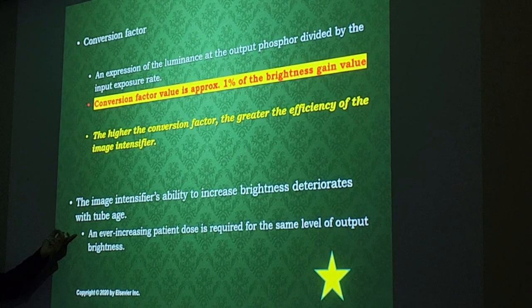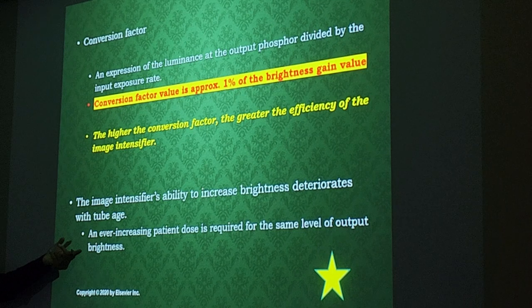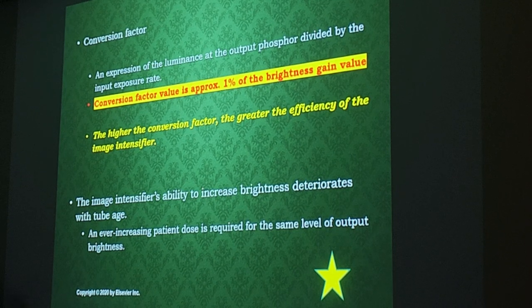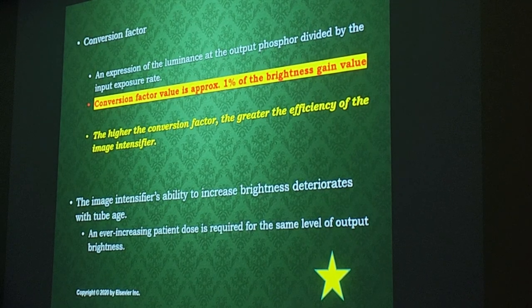To compensate for the aging intensifier, you would have to increase the patient dose — meaning increase the mA, which gives you more electrons. That's what you would have to do to get the same level of brightness. So as the intensifier ages, you need more radiation to produce the same level of output brightness.